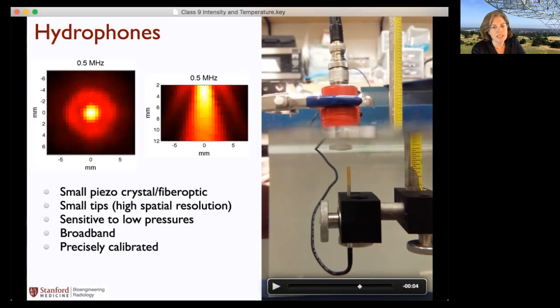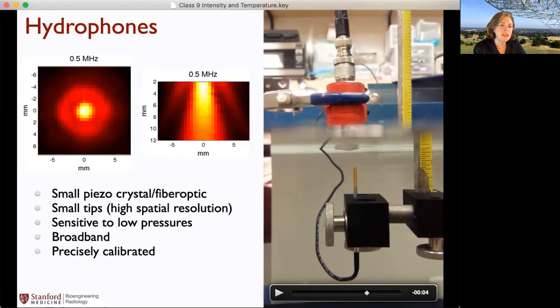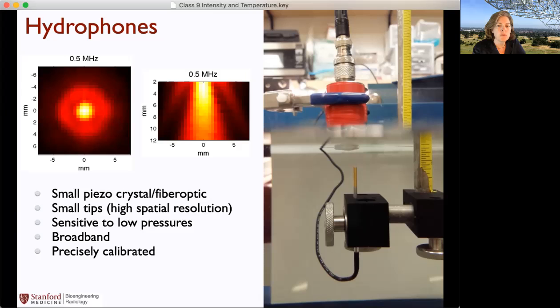All right, and as it's scanning around, it measures the pressure at each point, and then it can come up with a map, as you can see here. So it can scan around in 3D, and you can come up with a picture across the beam or along the length of the beam, as you can see here. And this is really nice. You can see here the side lobes on this single element transducer beam pattern.